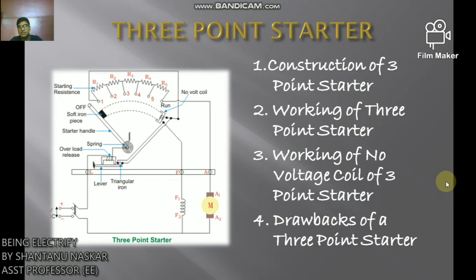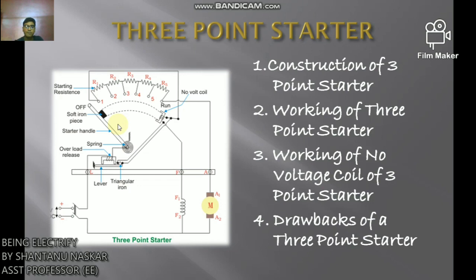When there is any supply failure, the current through the NVC is affected and it immediately loses its magnetic property, becoming unable to keep the soft iron piece on the handle in place. Under the action of spring force, the handle comes back to the OFF position, opening the circuit and switching off the motor. Due to the combination of NVC and the spring, the starter handle always comes back to OFF position whenever there is any supply problem, thus acting as a protective device.